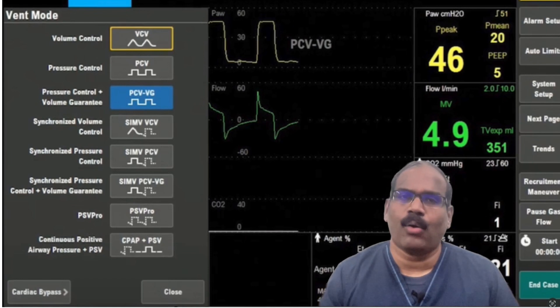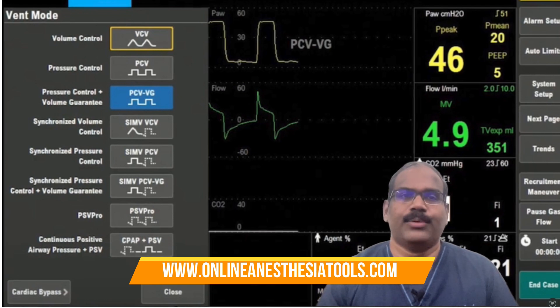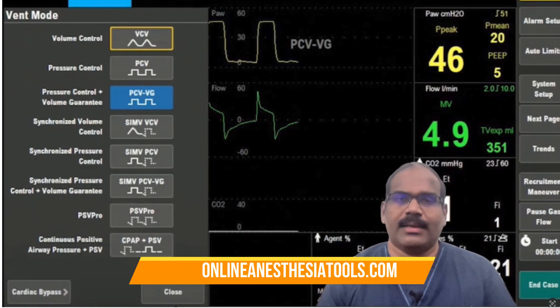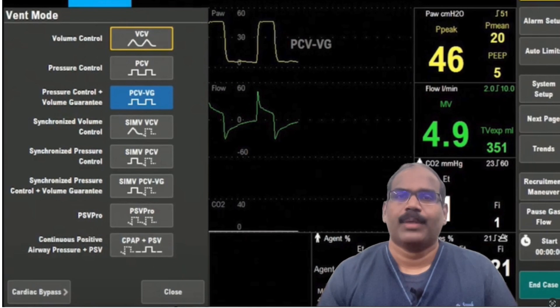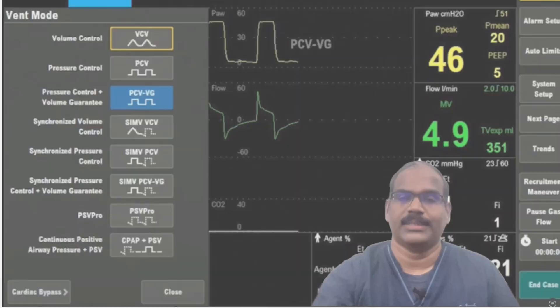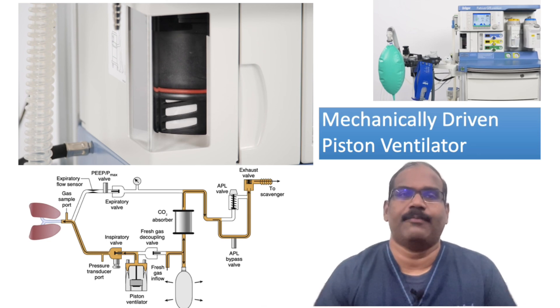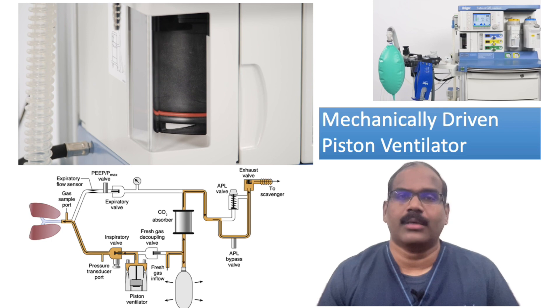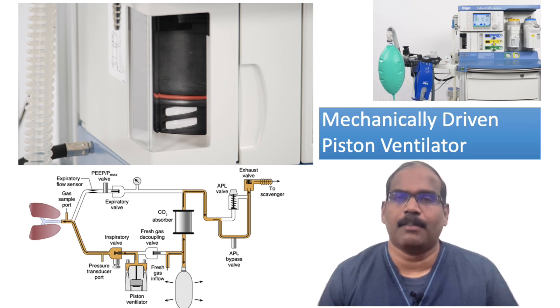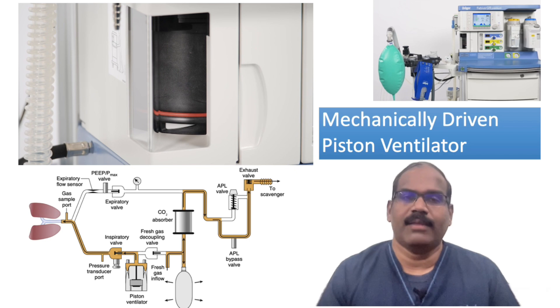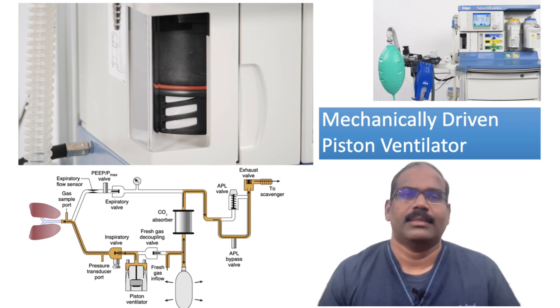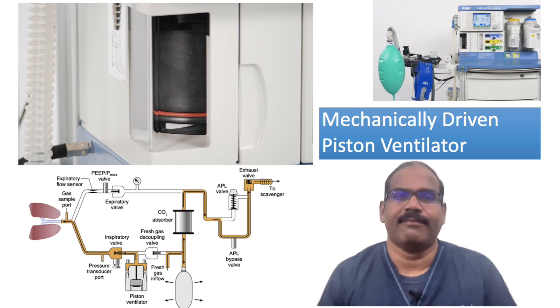Most newer anesthesia ventilators support almost all the modes of ventilation available in ICU ventilators, enabling continuation of the same ventilation mode for sick patients coming from the ICU for surgical interventions in the operating room. Mechanically driven, electronically controlled piston type ventilators use a computer-controlled stepper motor instead of compressed driving gas to deliver the tidal volume. These are single circuit ventilators because there is no separate ventilator drive gas circuit.